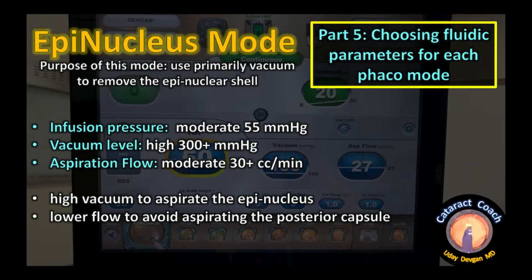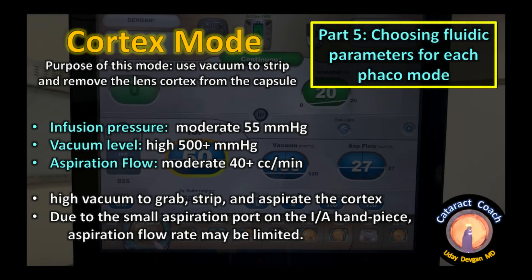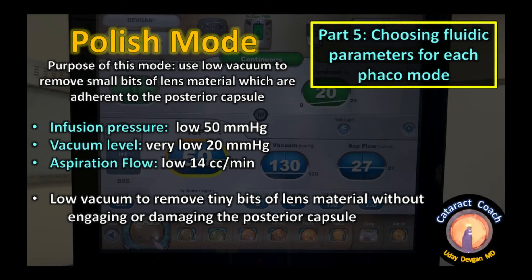Epinucleus mode uses primarily vacuum to remove the epinuclear shell: moderate infusion pressure, moderate flow, and relatively high vacuum. Lower flow is used to avoid aspirating the posterior capsule — we only want to aspirate the epinucleus. Cortex mode requires high vacuum to strip and remove lens cortex from the capsule: moderate infusion pressure, very high vacuum, and high aspiration flow. Keep in mind the IA port is small and may limit flow.